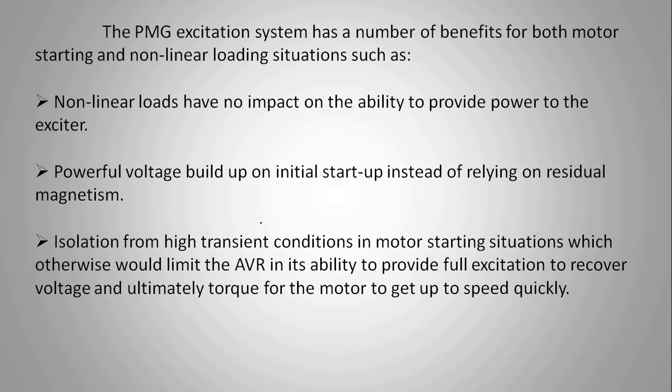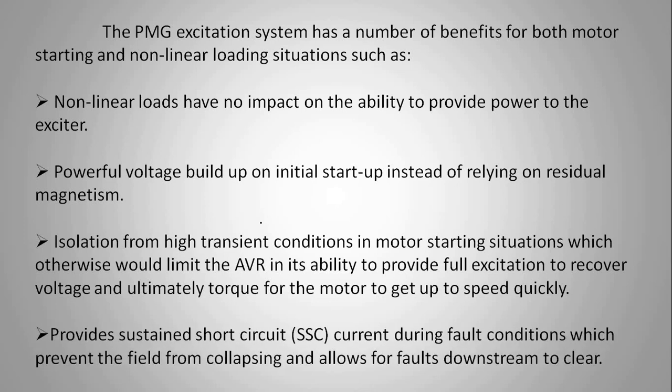In those transient conditions, the AVR is fed from a separate input source, the PMG, so the AVR will function very well. Then these transients will not have much effect on the generator operation or motor operation during the transient period.